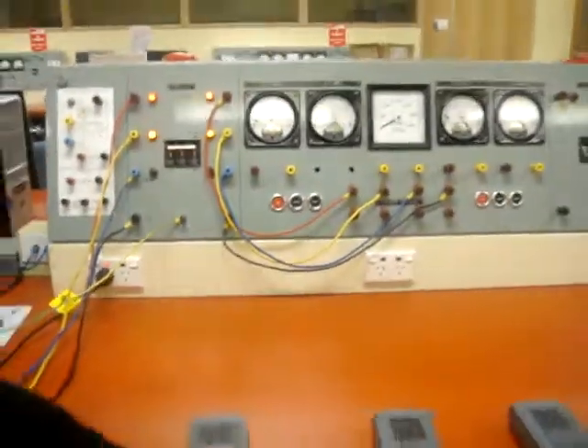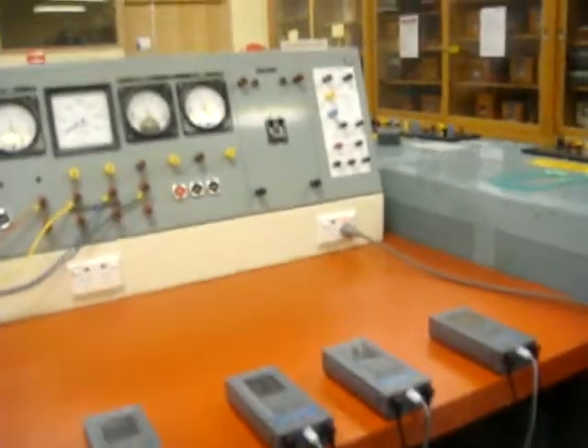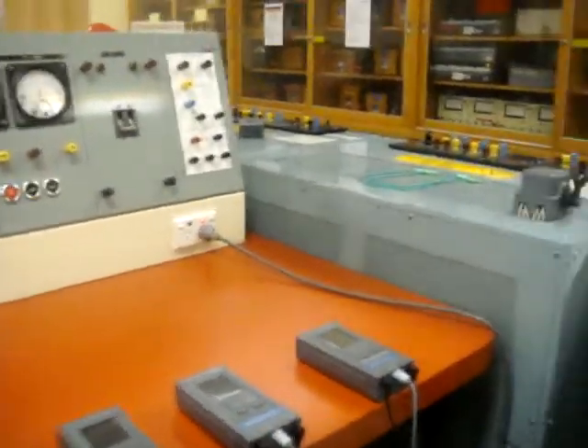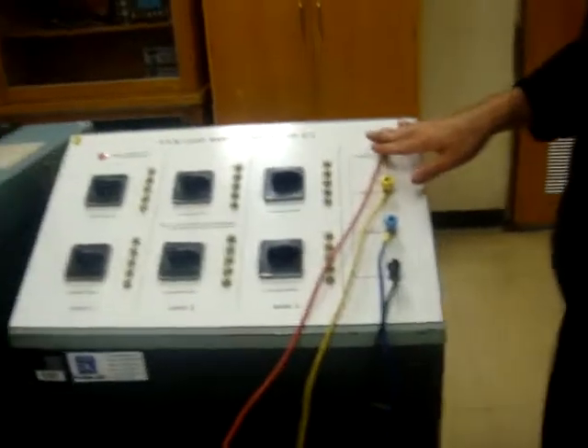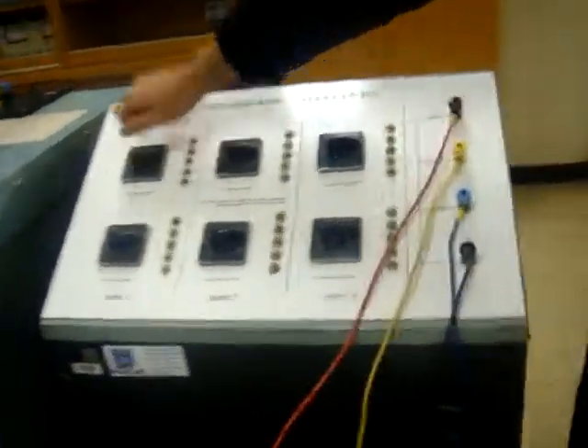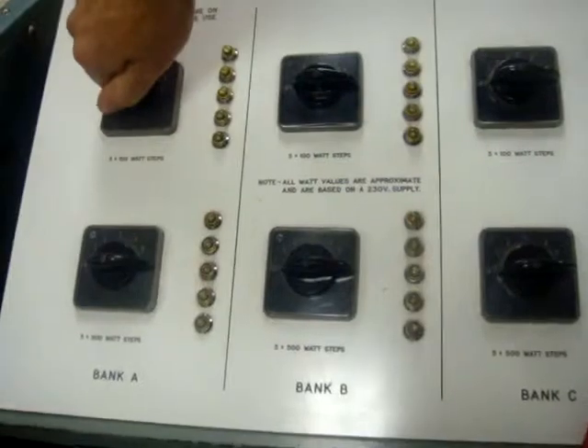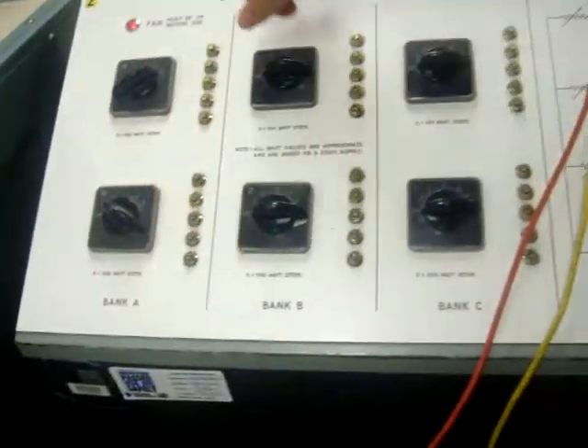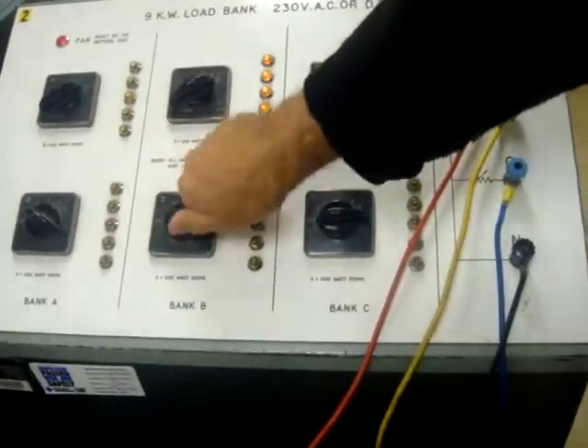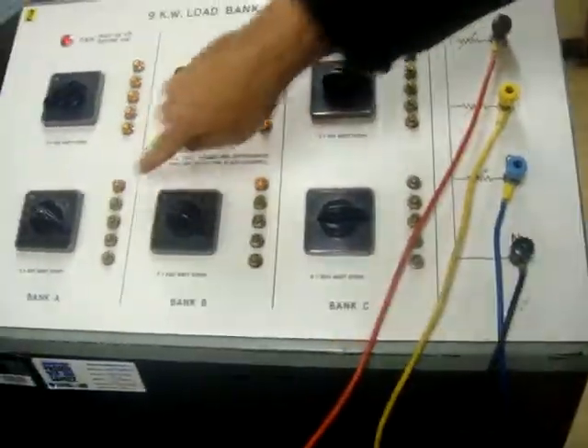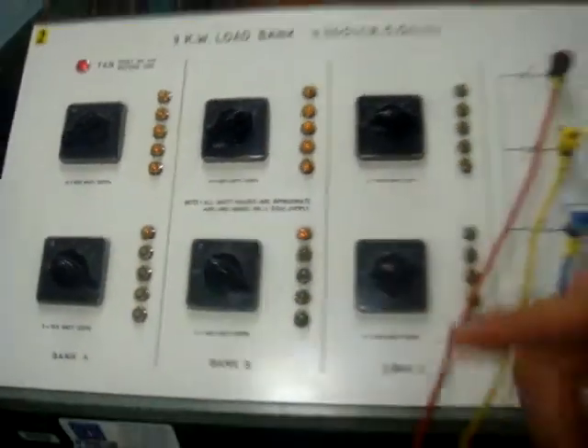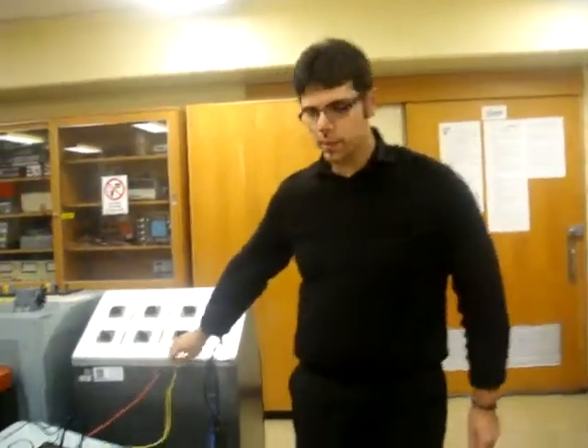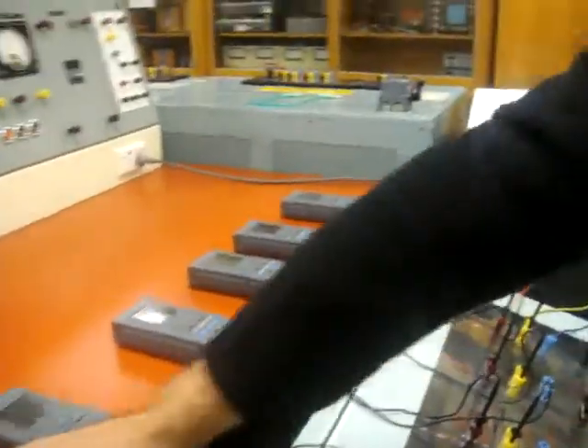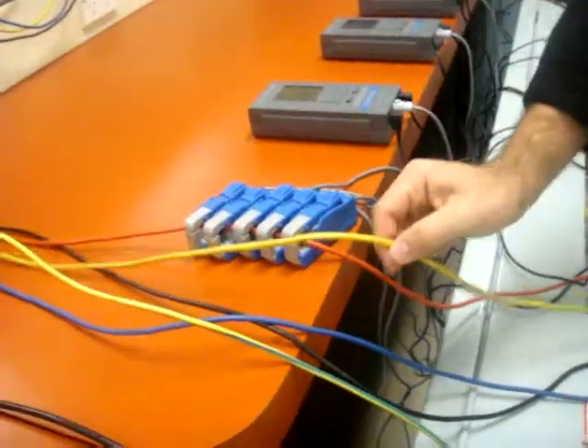At 415 volts, we now go to our load bank and connect the red and yellow banks to 1 kilowatt power each. This makes the lights flash on. Also, I must note that since we are connecting the red and yellow phases, we need each of the 5 power meter couplers connected to either the red or yellow phases.